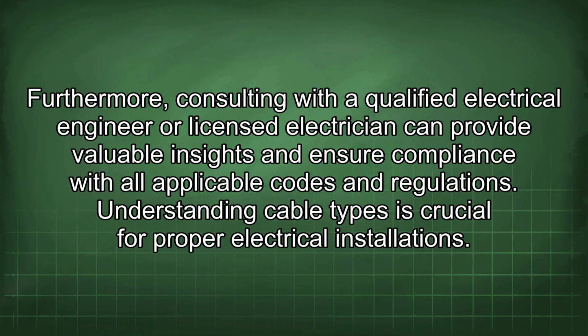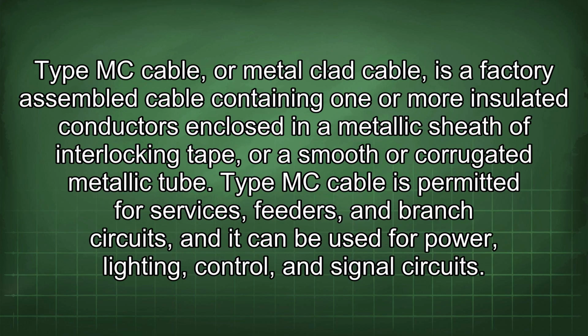Understanding cable types is crucial for proper electrical installations. Type MC cable, or metal-clad cable, is a factory-assembled cable containing one or more insulated conductors enclosed in a metallic sheath of interlocking tape, or a smooth or corrugated metallic tube. Type MC cable is permitted for services, feeders, and branch circuits, and it can be used for power, lighting, control, and signal circuits.